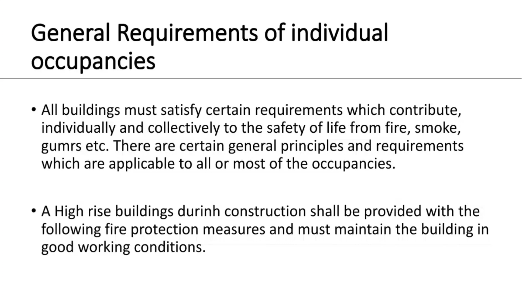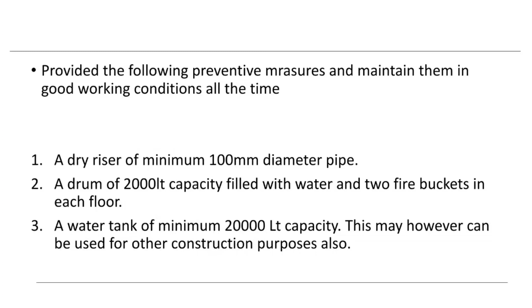See, the first is a dry riser of minimum 100 mm diameter pipe, and second is a drum of 2000 liter capacity filled with water, and 2 fire buckets on each floor. A water tank of minimum 20,000 liter capacity. This may however be used for other construction purposes also. Okay, now let's go to our next slide.